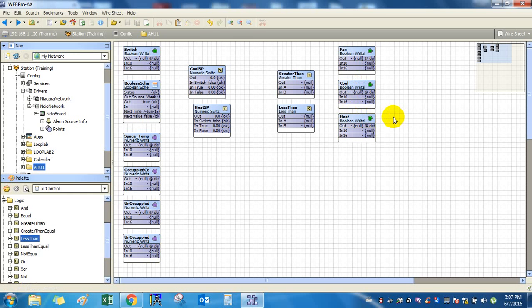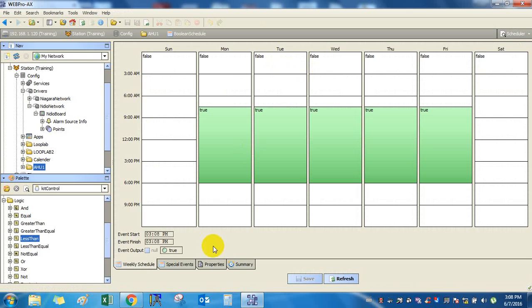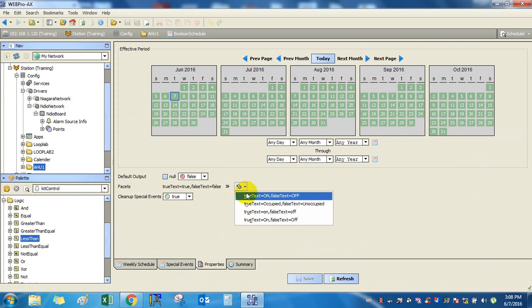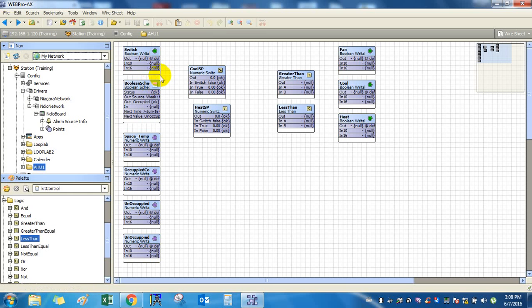So here your boolean schedule will tell you whether you are in unoccupied or occupied mode, depending upon which we will select the set point, whether we want the occupied set point or unoccupied set point. We will decide this for both heating and cooling. So link the out slot of this boolean schedule to in switch of your cooling set point. What this numeric switch does is, whenever one is coming through this in switch, it will send the true value, else it will send the false value.